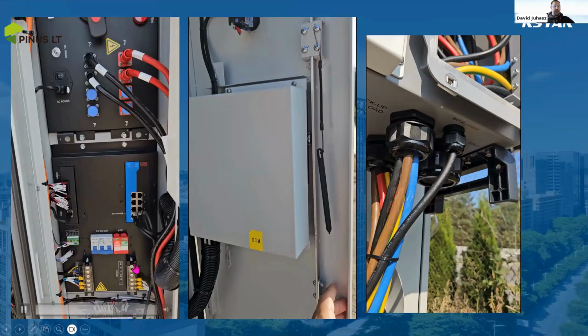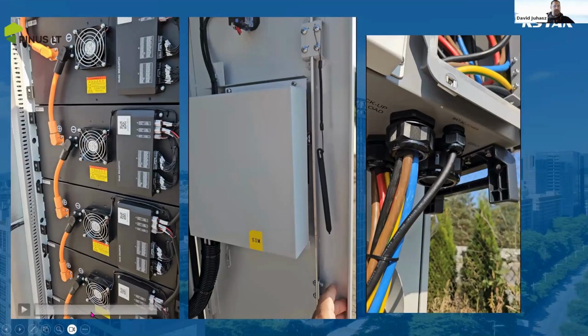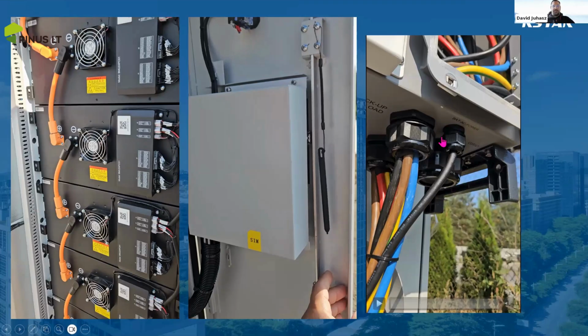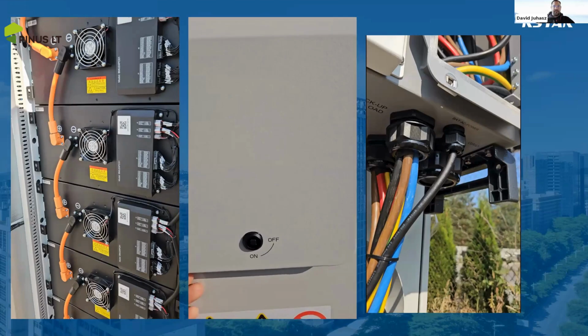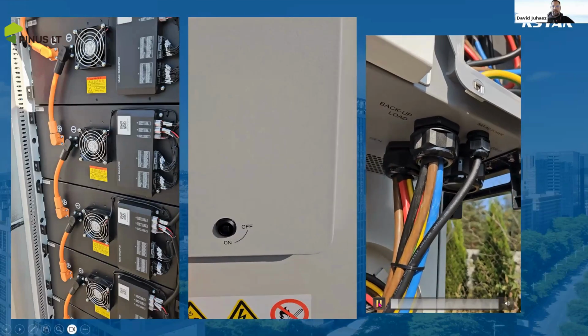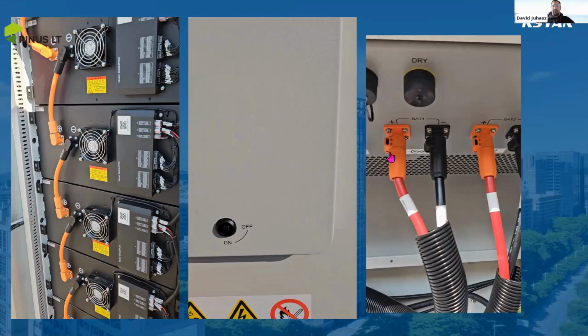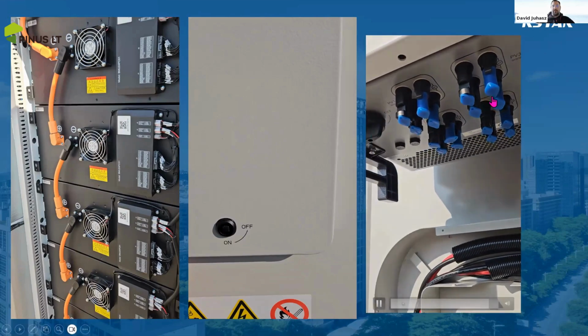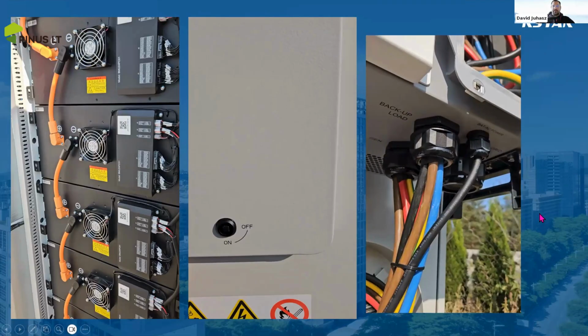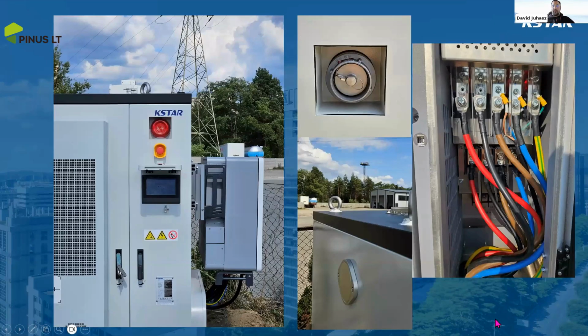We see the high voltage box, the switch device, the battery cabinets inside. This all comes together manufactured, and on the site, only the inverter needs to be attached. These are the battery connections, the communications, and the PV can be connected here. Okay, some pictures. These are the dedicated inputs of the KSC50DP2 inverter. So there is one for the grid, there is one for the backup load, and there is one for the diesel generator.